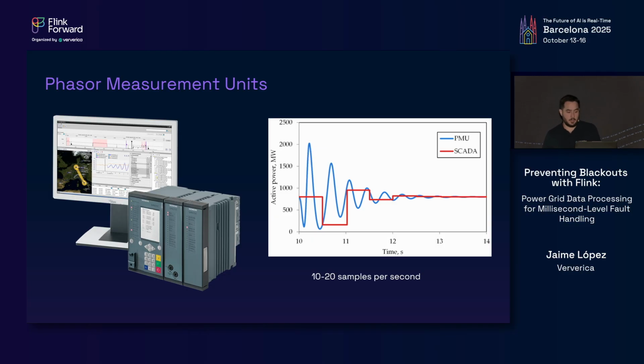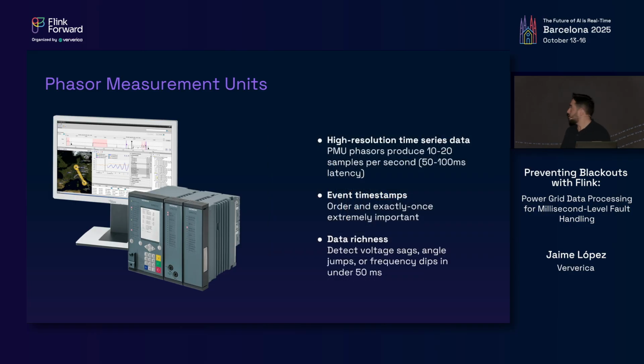And you install these PMUs to not just report the steady state condition, but this dynamic capacity of the grid, to capture these events as they unfold. They are extremely useful to spot these oscillations, these drops, these sags, as they spread or before they spread. So, as I said, high resolution data: in contrast to SCADAs, you're suddenly going to have real data with 50 to 100 milliseconds latency, which is 10, 20, 50 times faster than a SCADA can.